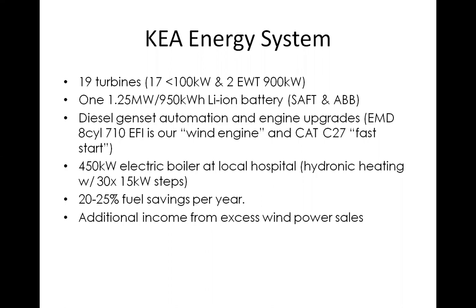We also have a lithium-ion battery. It's a 1.25 megawatt inverter by ABB, coupled to a 950 kilowatt hour lithium-ion battery made by SAFT. Between the two, we have essentially a 1.25 megawatt genset, we call it. We kind of treat it like a small generator that we can start and stop immediately, and it's come in handy for spinning reserve and acting like a UPS.